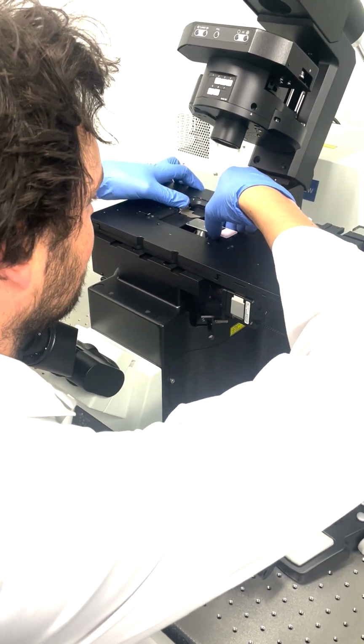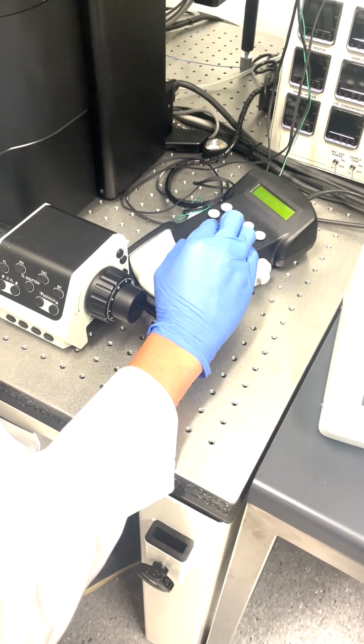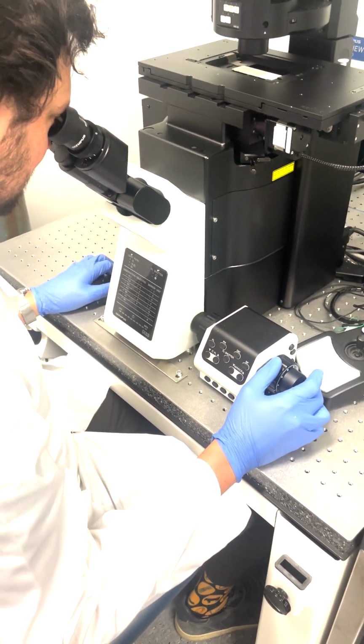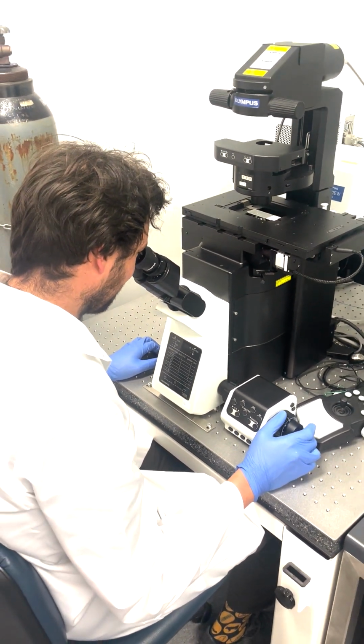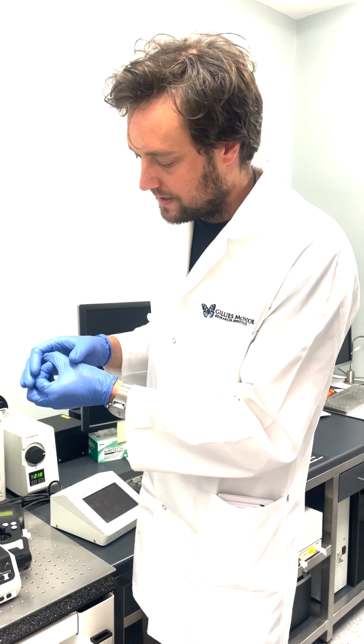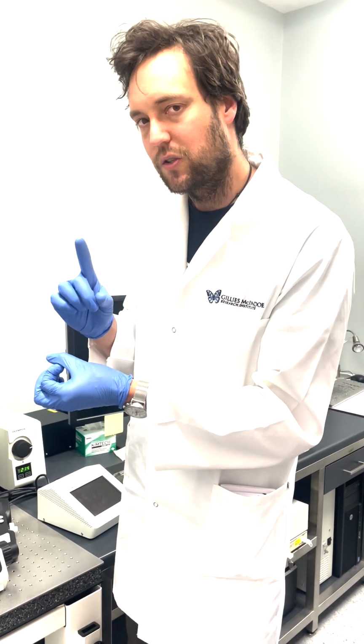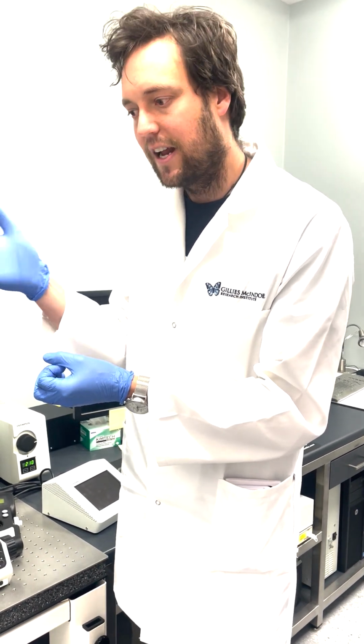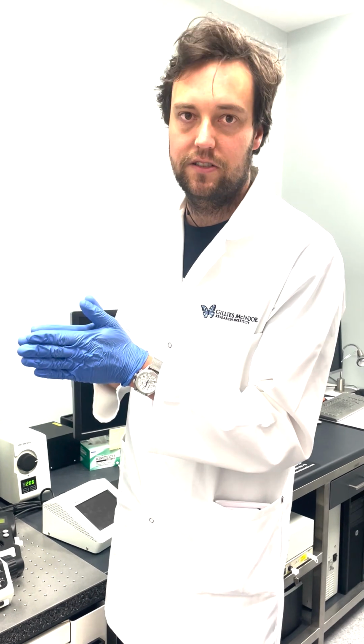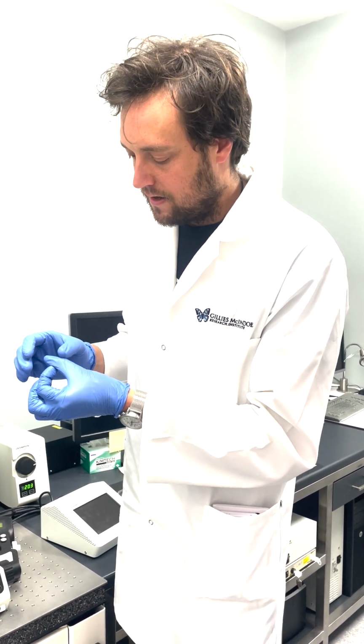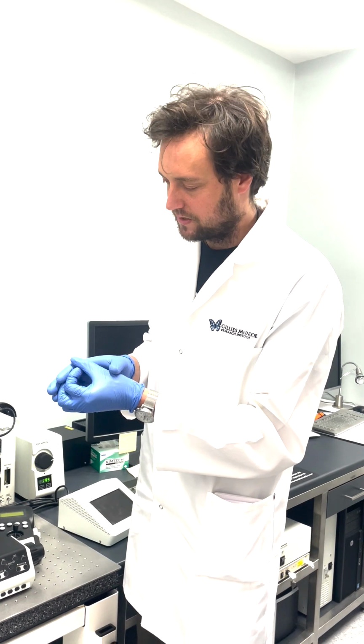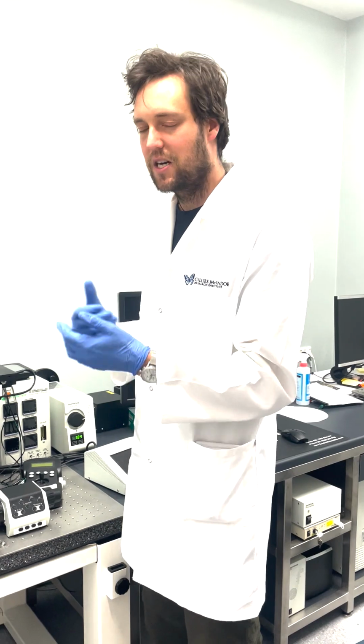If you think about a camera in our phone or an actual camera, you have an area which is the sensor. And if you have a 3 megapixel camera, that's 3 million individual pixels that you're capturing on that space. This microscope has that same area dedicated to a single pixel at a time. What it does is it has mirrors and actually scans across the image, capturing 1 pixel at a time. The advantage of that is that because you're dedicating the entire area to 1 pixel as opposed to splitting it up across your millions of different pixels, you get much more sensitivity. So because you're dedicating all of that area to 1 pixel, you get much improved sensitivity.